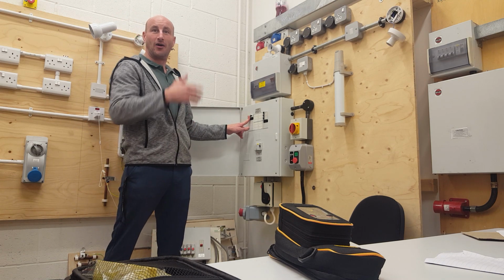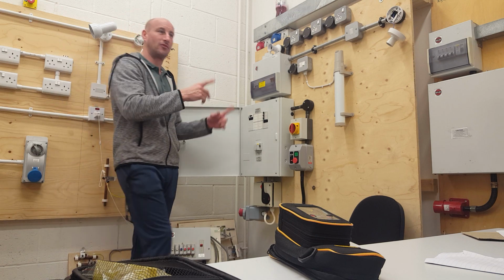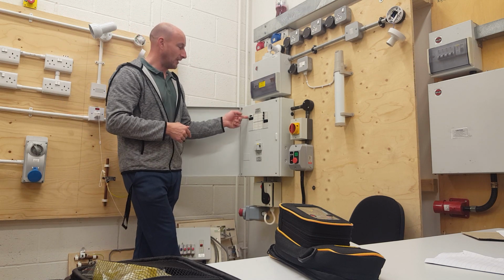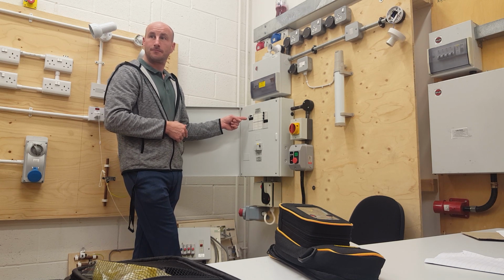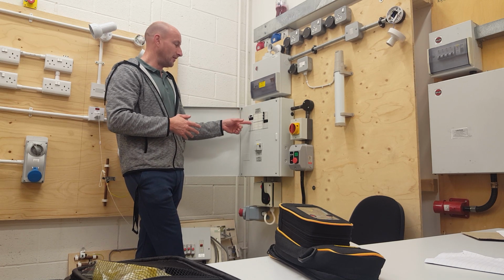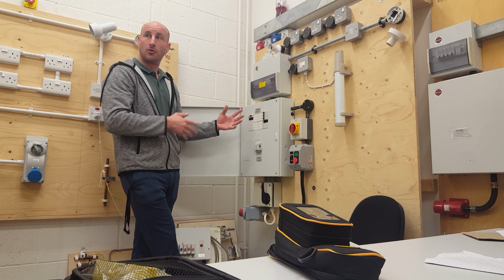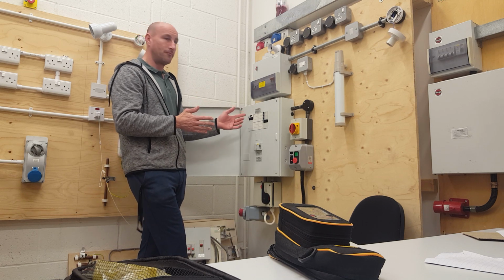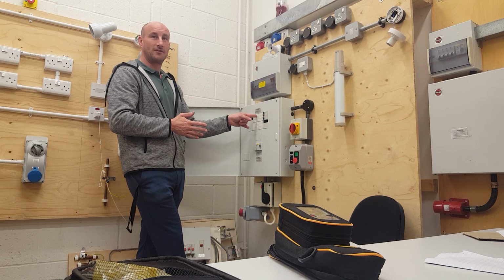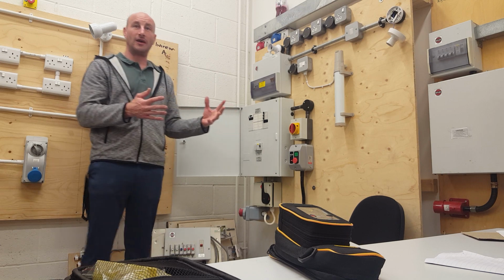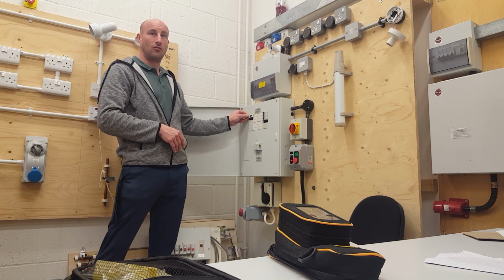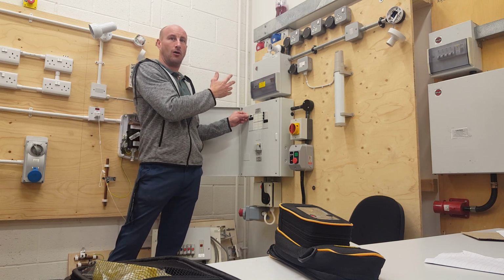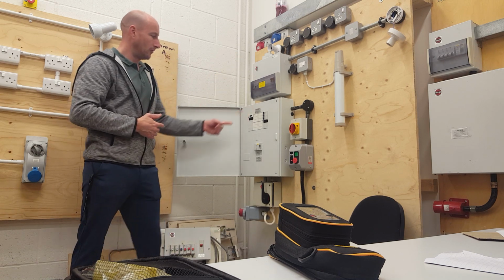I could hear people saying the right answer, but I wanted to get to the ones that actually say the wrong answer. So yeah, the single phase MCB. If there were 2 of them, there'd be another one of those boxes somewhere else in the house. Potentially there might be a lighting circuit coming off here, there could be anything. Normally it says next to it, but it might not, there might be nothing written there. So we think it's that one, because it's a 63 amp, that's got to be for a large feed for another board. So we're going to switch that off.